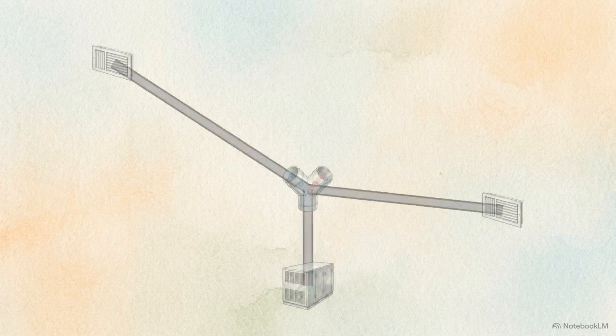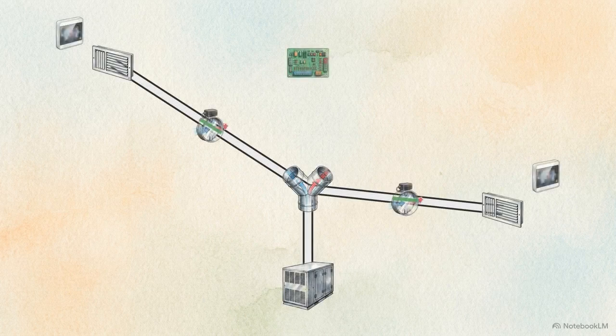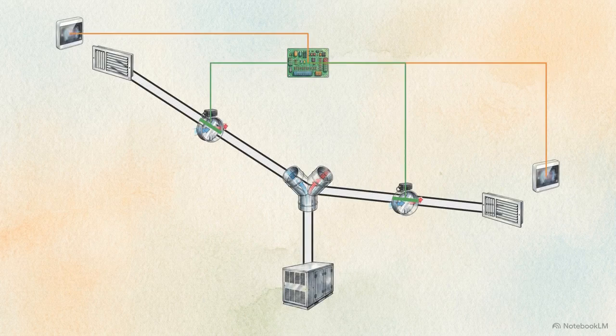When a technician retrofits your system, they install two hidden components that make zoning possible: a central zone control board and a series of motorized dampers. The zone board acts as the brain of the operation, processing independent temperature requests. Based on those requests, the board sends an electrical signal to the motorized dampers, which physically rotate to block pathways. If the downstairs is cool enough, the system shuts the dampers to that zone, redirecting the air strictly where needed.